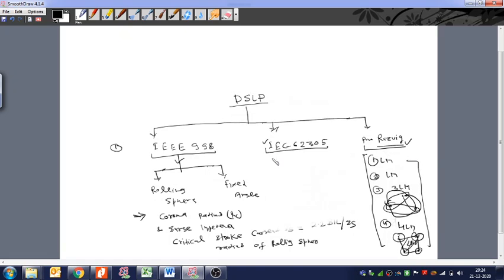In IEC, we discussed that we take the annual thunderstorm days per annum. This is the first input. Thereafter we calculate the lightning density Ng. This is 0.1 into Td, where Td is the thunderstorm days. Thereafter third we calculate the collection area, Nc.